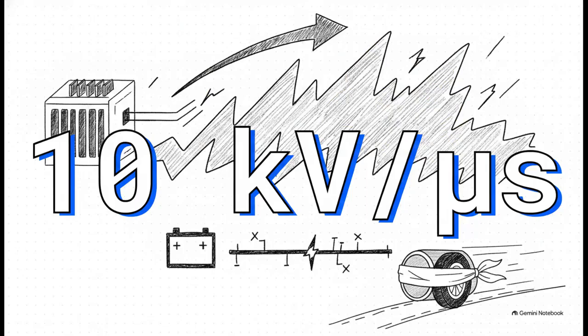Let's zoom in on that first dimension for a second. Inside these high-density power enclosures, silicon carbide MOSFETs are switching at incredibly high frequencies. This generates some massive voltage transients. We're talking about a change in voltage over time, or dV/dt, of 10 kilovolts per microsecond or more. That is a massive wave of electromagnetic noise injecting strong common mode interference right into our low-voltage CAN lines. And if the network loses frames because of this physical noise, the motor controller is forced to rely on old, outdated power limits. It's literally driving blindfolded at 100 miles an hour.